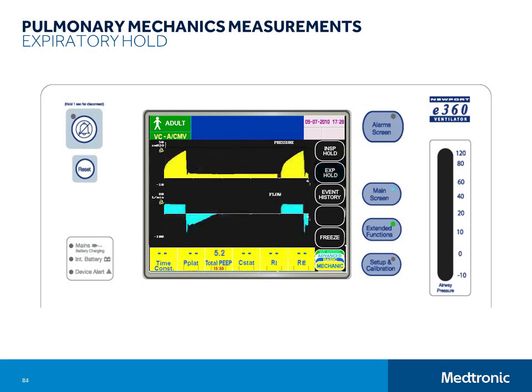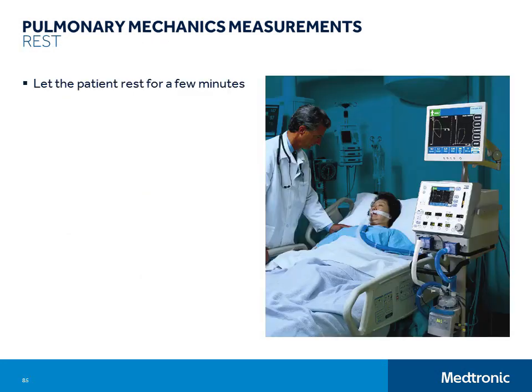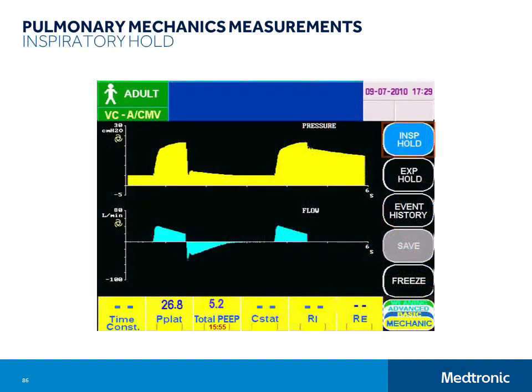Next, touch and hold the inspiratory hold button during inspiration and continue holding until past when the breath is completed and you see pressure equilibrate on the pressure waveform. Then let go. During an inspiratory hold, no flow is delivered and gas is prevented from exiting the patient's lungs. The airway opening and alveolar pressures equilibrate. If patient exhalation is passive and the inspiratory phase is held until a quasi-steady pressure is achieved, the circuit pressure will provide a reasonable estimate of the alveolar pressure.